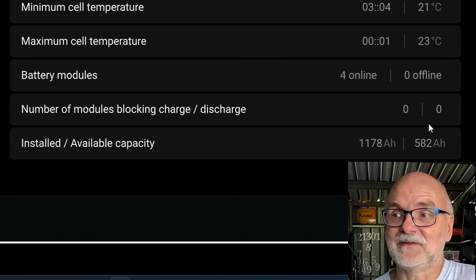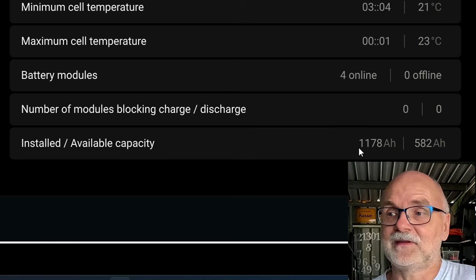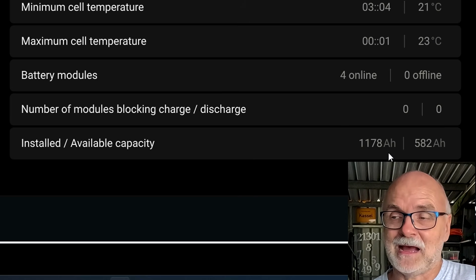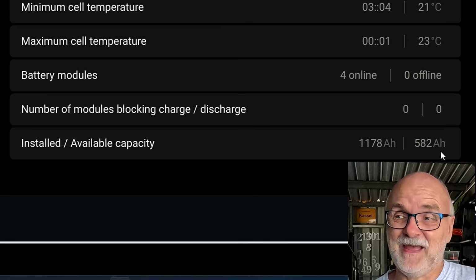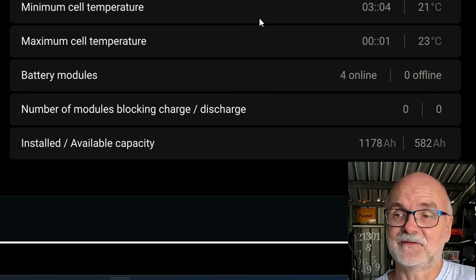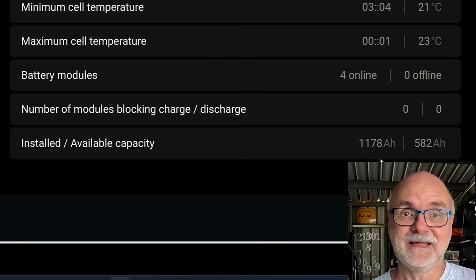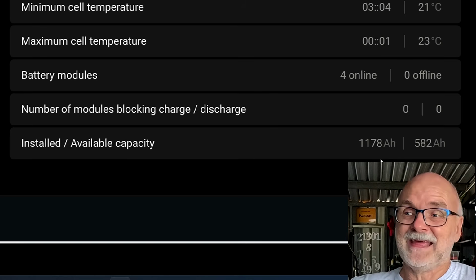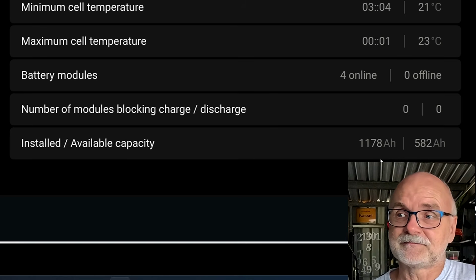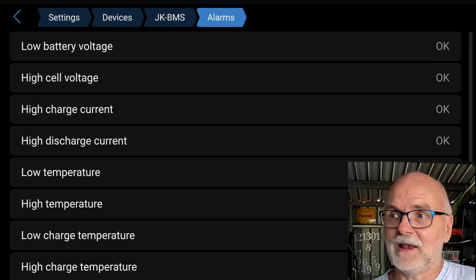None of the batteries is blocking the charging and discharging, and we have an installed capacity of 1178 ampere hours. We have 582 ampere hours available. So perfect, this is all good. This information is coming from the master BMS as well. It collects all the information of the connected batteries. Of course, at the moment we have no alarms.